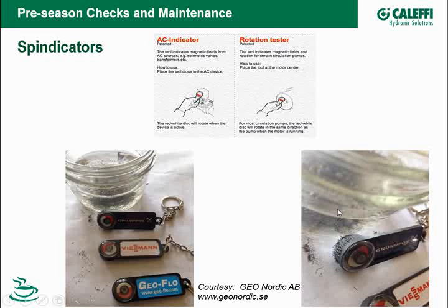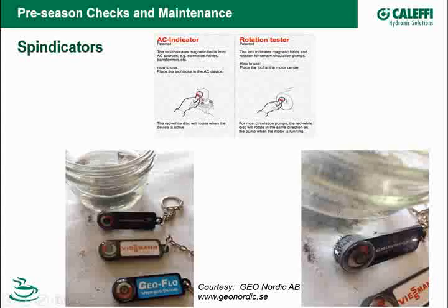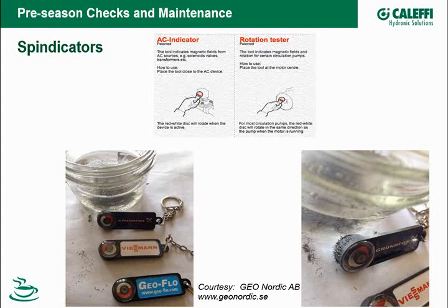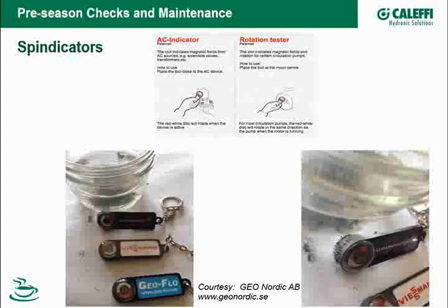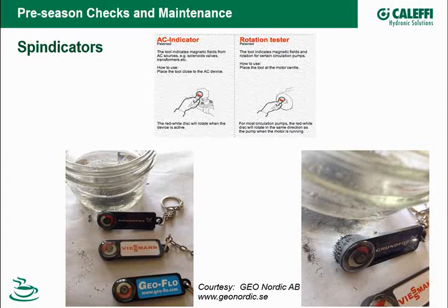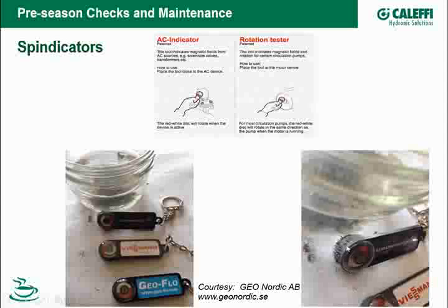Another thing I found it was good for, if you're taking a sample of your water, one of the things that we're concerned about now, especially with ECM types of pump, is that we don't have a lot of this fine iron ferrite, these tiny magnetic particles that can stick inside the system. So if you take a sample of the fluid out, put it in a little glass or plastic cup or something like that, you can take a little spindicator and it'll tell you if you've got a magnetic particle in there.